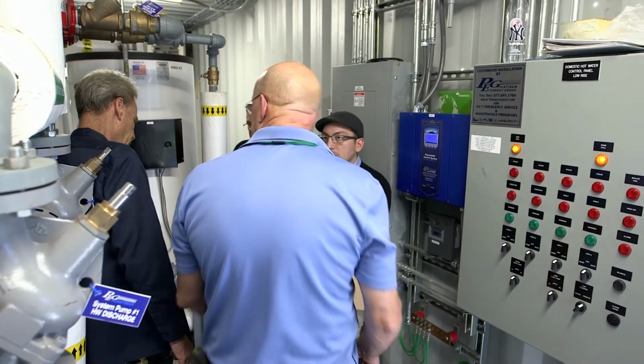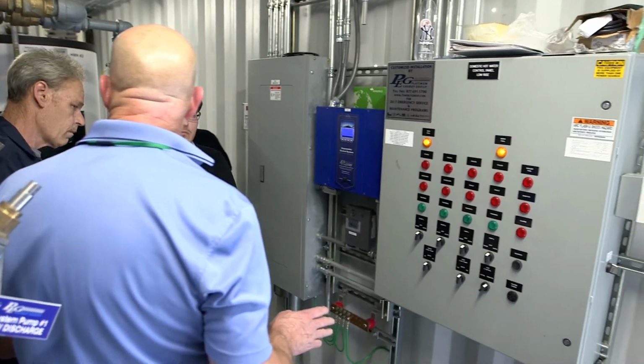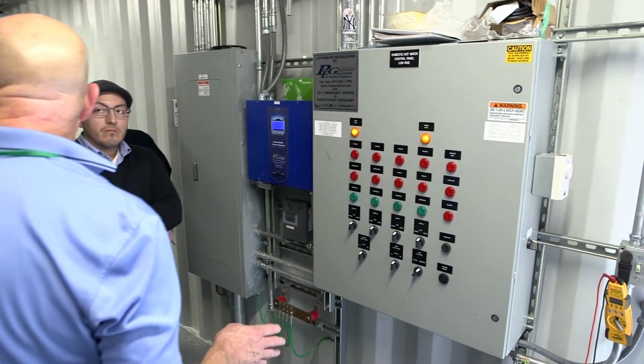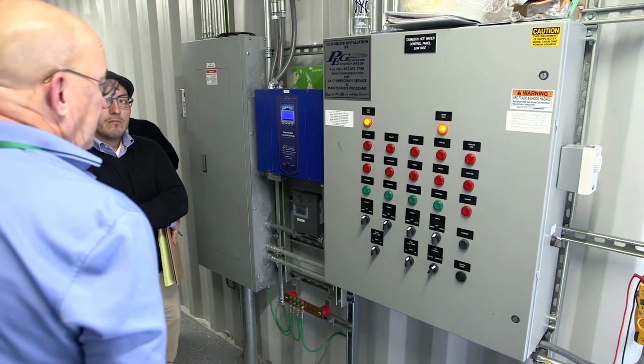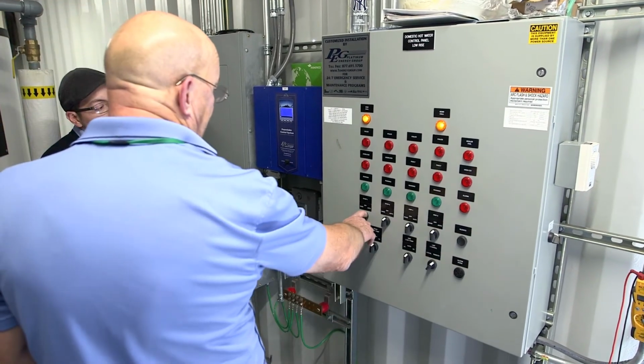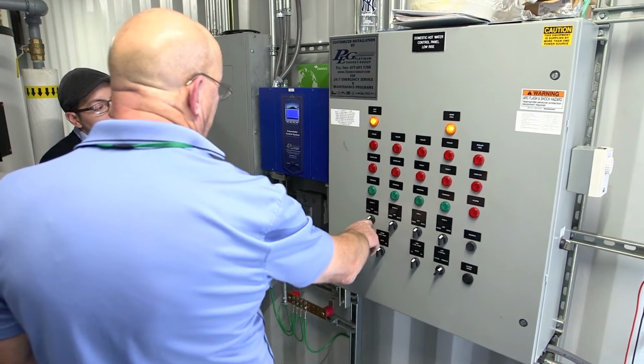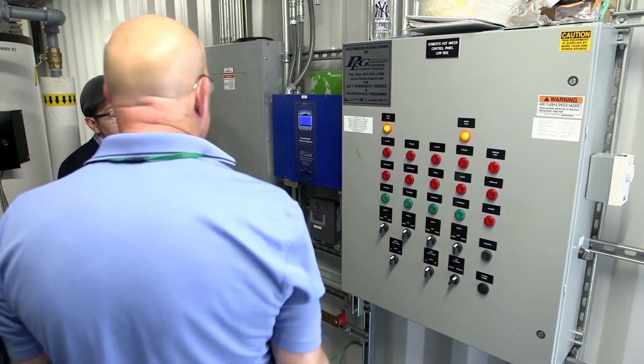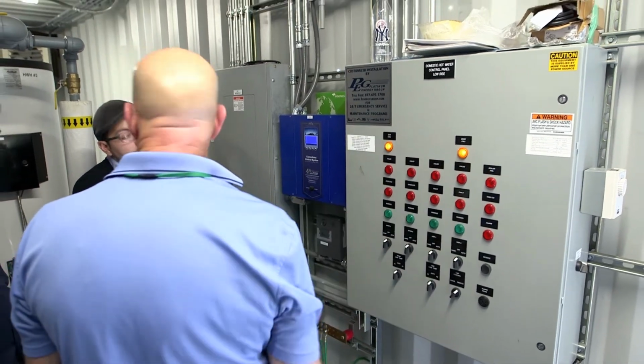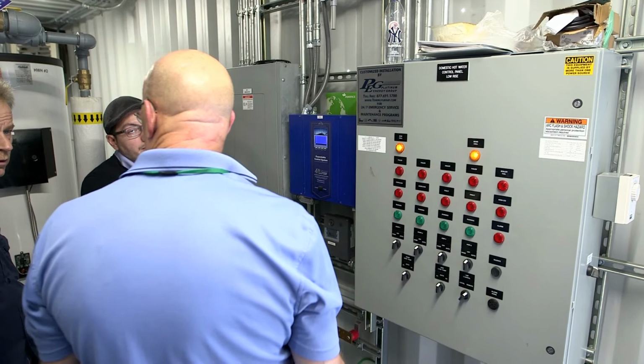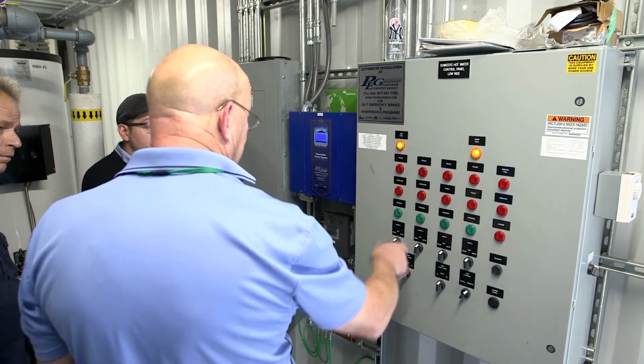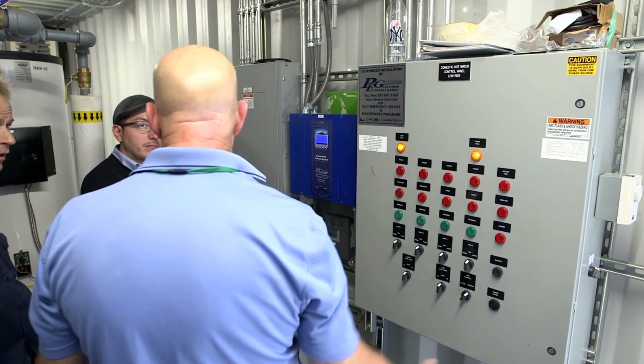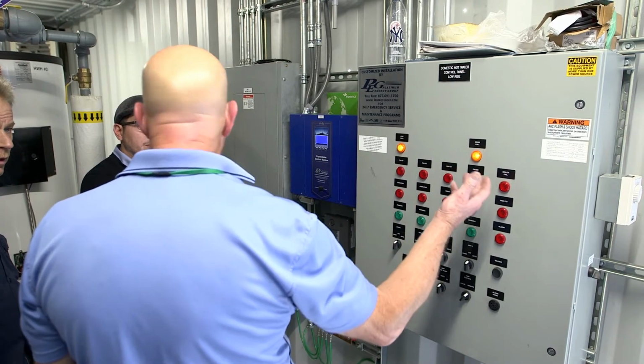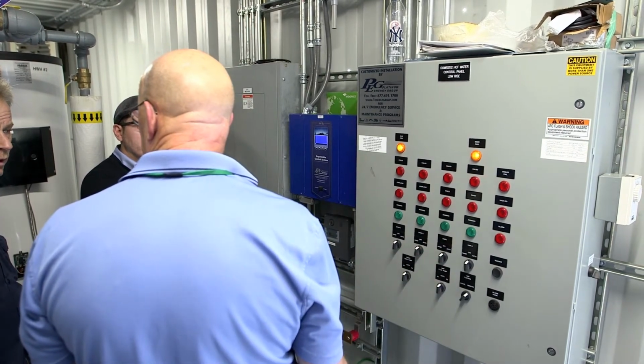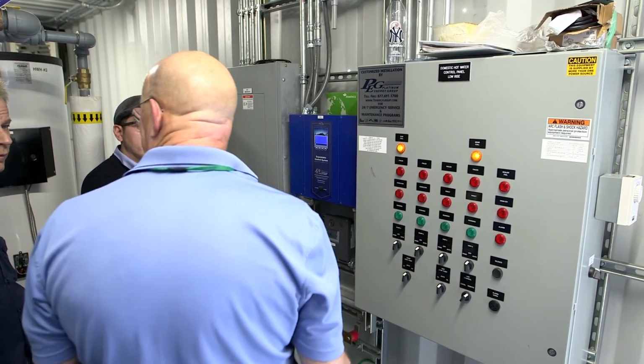It controls, because both pumps have to run simultaneously. They can't run without each other. So you're isolating at that. You leave it in auto at all times. If for some reason you have a call for domestic water and the pumps aren't running and you don't know why, put them into hand. You put it into hand, it comes on, there's a relay or something wrong inside the panel, it's got to be replaced, but you have hot water for now.